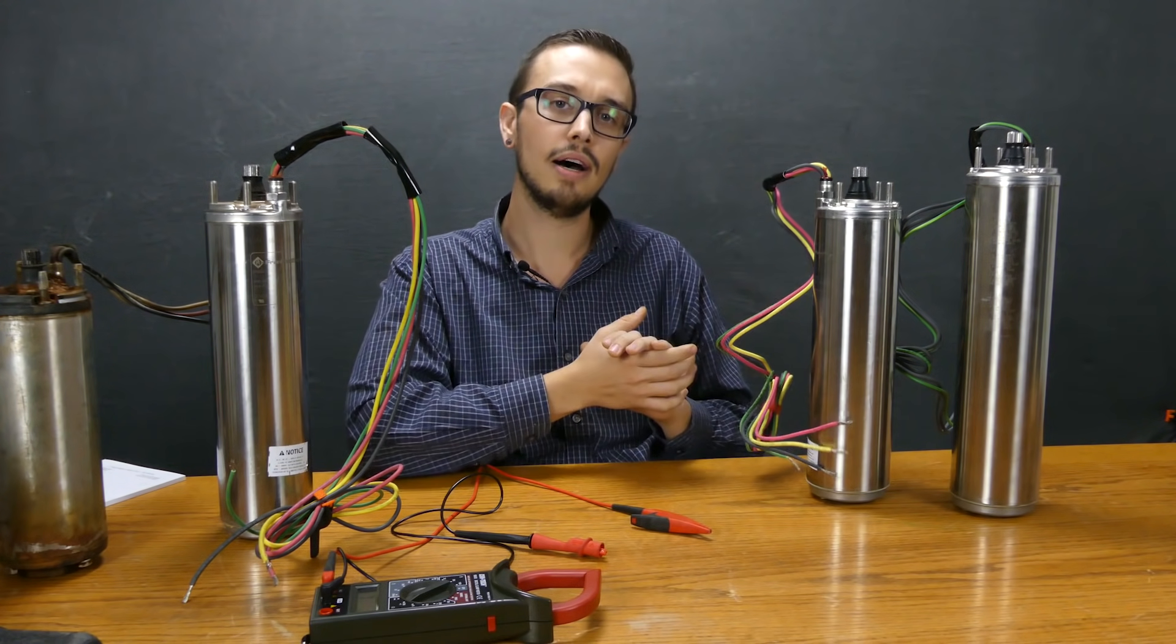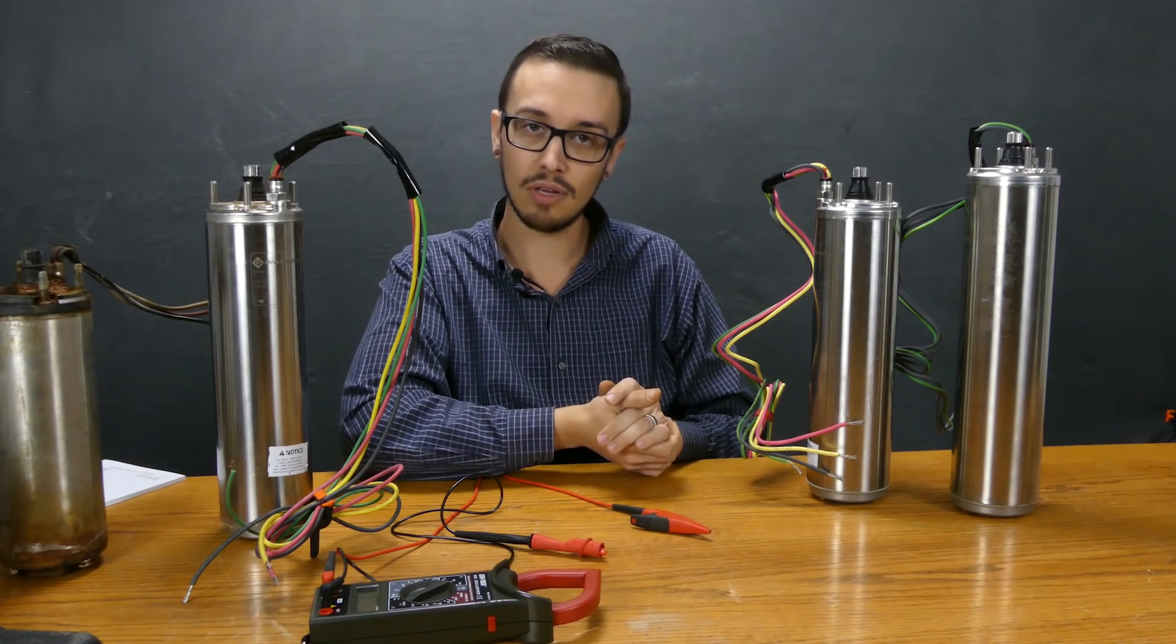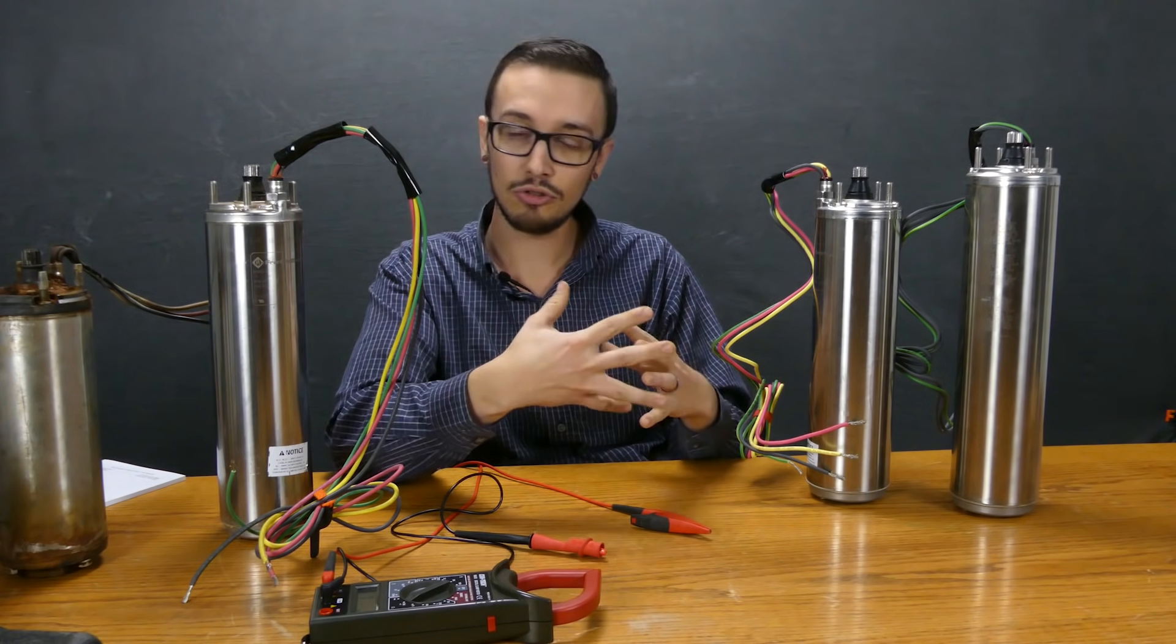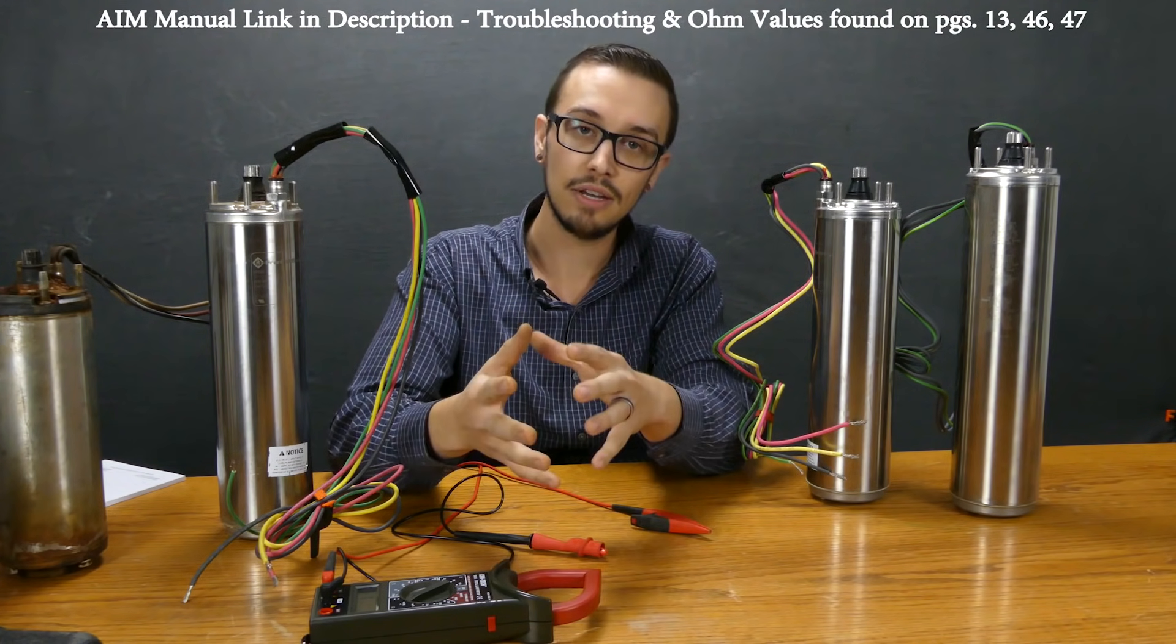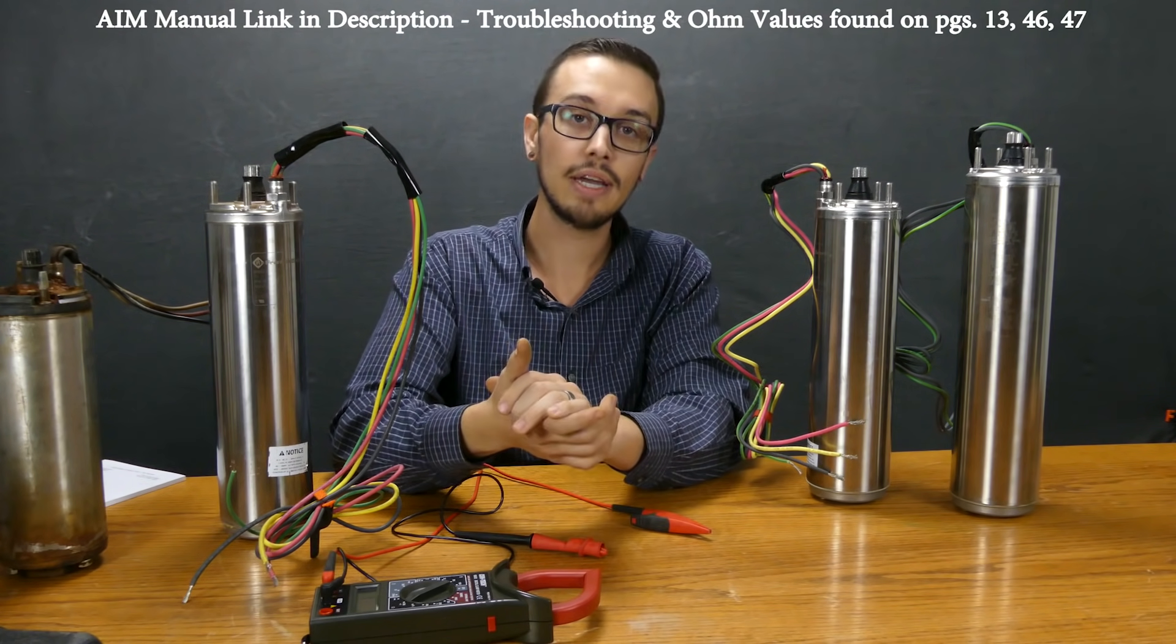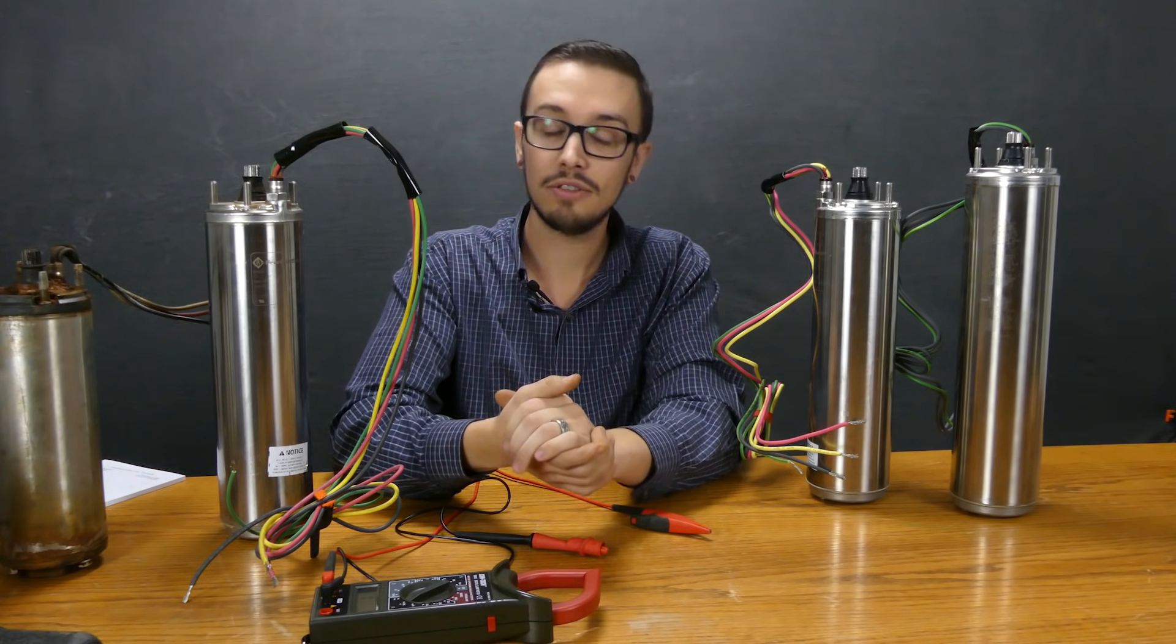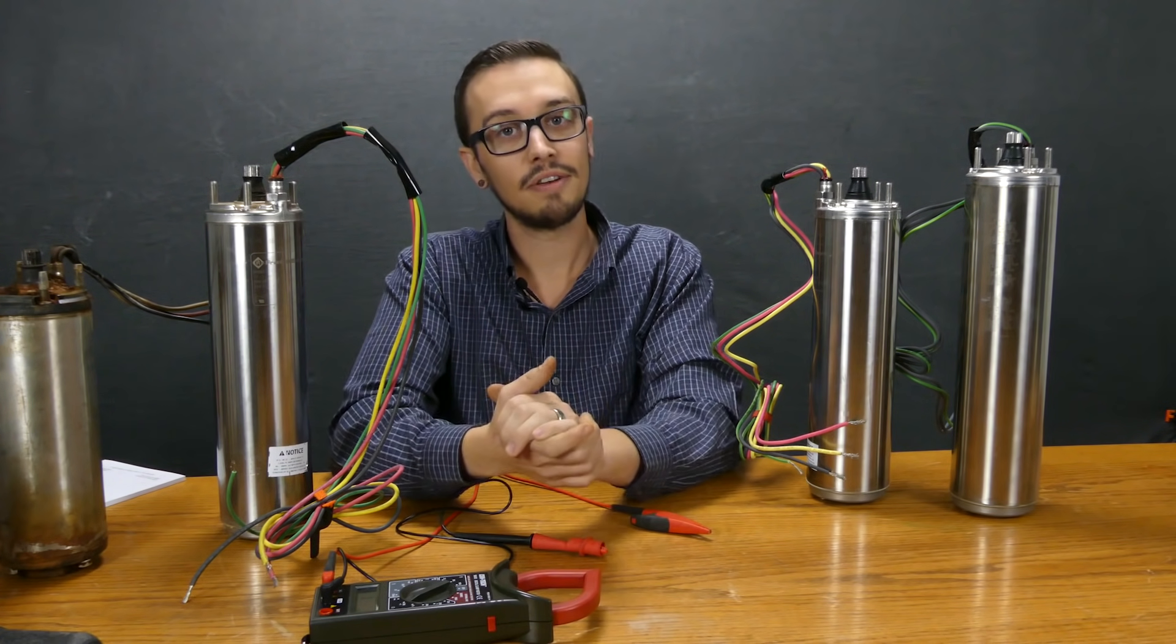Also keep in mind when you are testing down the well you have to take into account the voltage drop that occurs. Once again I'll refer you back to the AIM manual that does have a chart in there. So if you know the depth of the well, you know the length of the wire essentially, and it's going to give you an adjustment on how much you need to adjust each one of those readings. So keep that in mind and I hope that this video helped you. We'll see you next time.